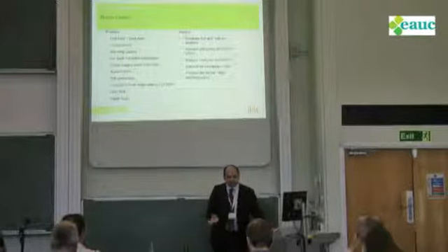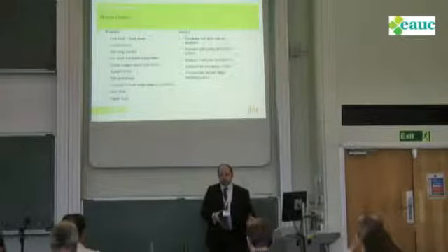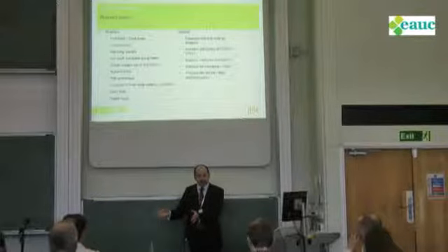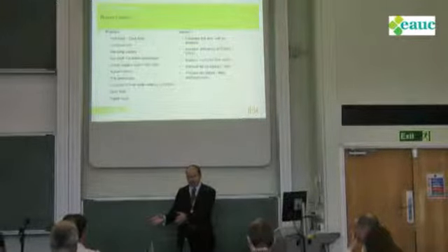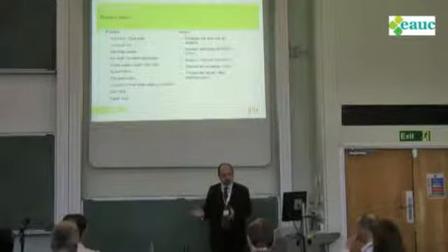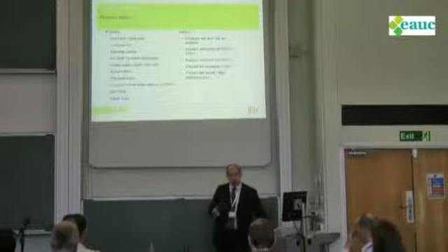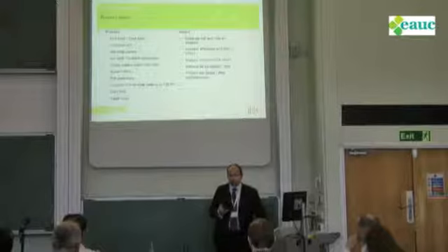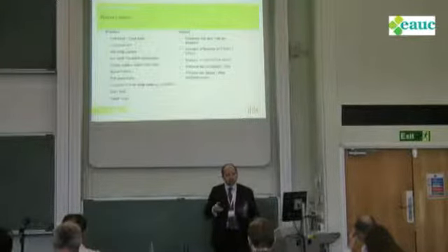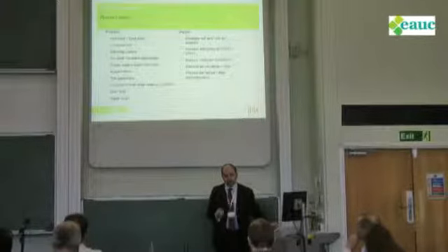There's two ways of fixing it. One is to move your racks further away and position your grid tiles further away so that you haven't got this velocity problem. And the other way is to put a baffle in underneath your handling unit, where you can reduce the speed, say, to 30%, and therefore you're not going to have the problem with velocity.